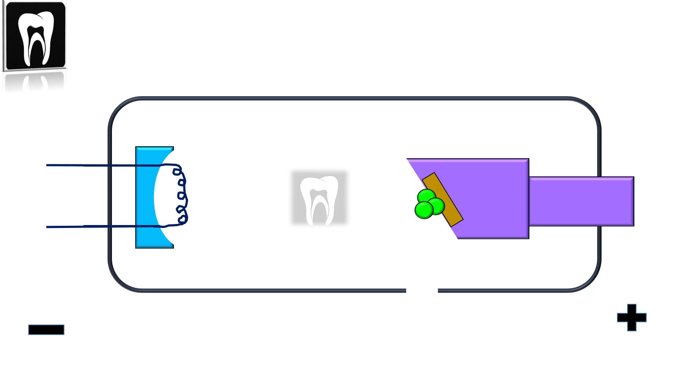The positive terminal of the X-ray tube is called the anode. Remember that it attracts the negative electrons—the anode must be positive to attract them. The anode consists of a tungsten target, and we have a copper stem in the anode that allows heat dissipation.